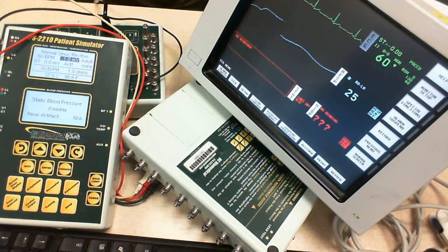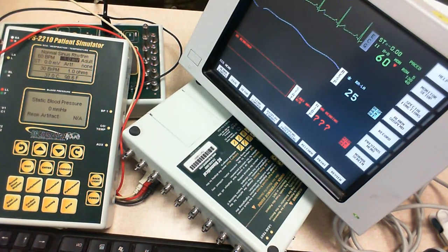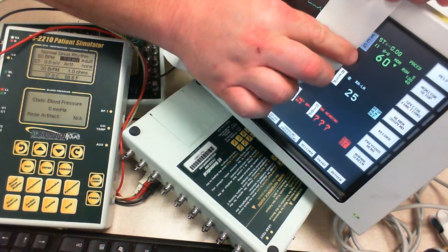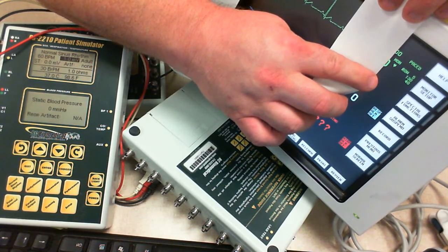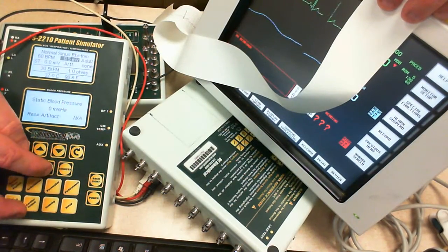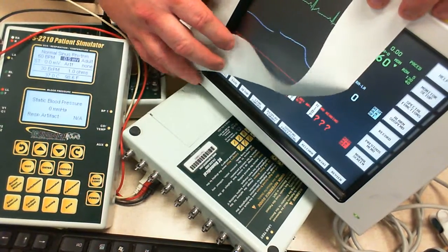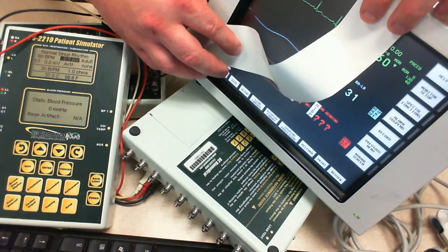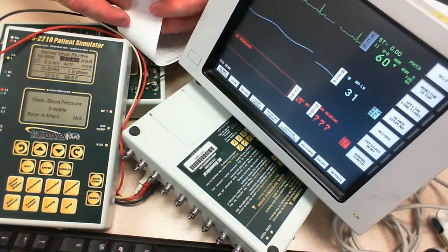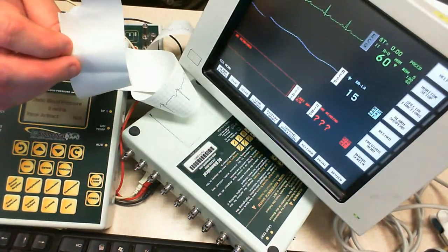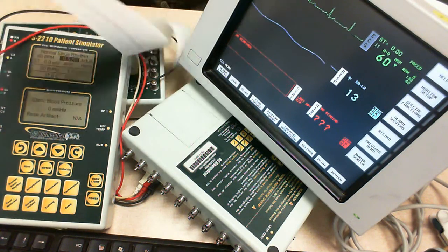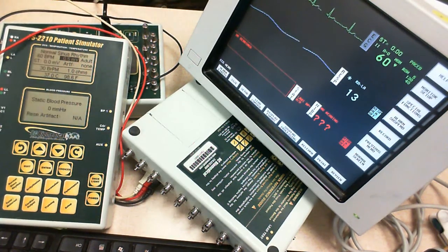Let me do this again. I'm going to set it back to 1. Notice that at 1, it's going to take a certain amount. Now, I've actually put a sheet of paper next to them and measured them, and compared those notches between the top of the QRS and the bottom of the QRS to the next one. I'm going to lower it and hit enter. You'll notice that the waveform is definitely much smaller. Then just compare the notches to that. If necessary, you take the sheet of paper and fold it in half and see where your notches are based upon that line. Does that make sense? That'll be a good way for you to compare what a full-sized and small-sized wave looks like. And that's how you can do a gain check.